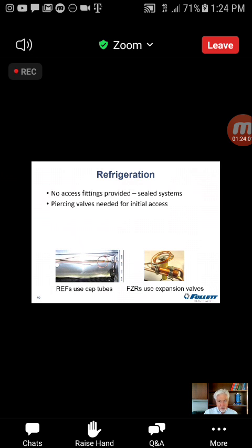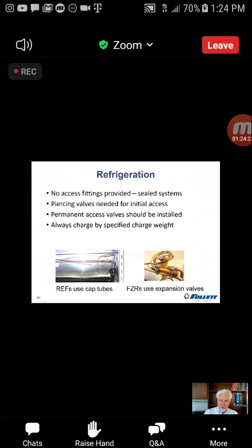But as I'm sure you know, the issue with piercing valves is that over the long haul, they're not very good at keeping the Freon where it belongs. So permanent access valves should be installed as you're concluding your work. We should put those on before the final evacuation and recharge is done. And when you're recharging, please always charge by weight. Do not charge by pressures.